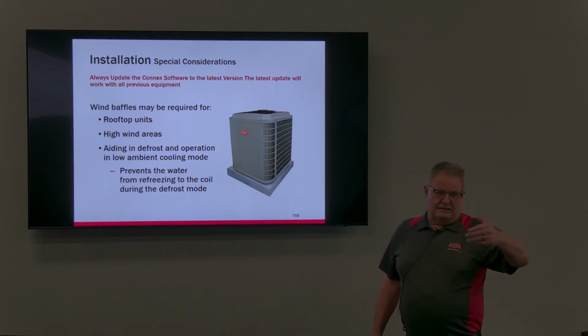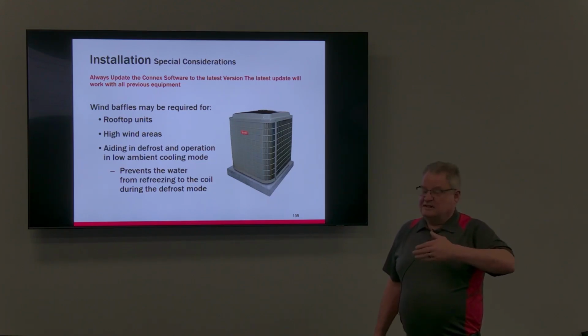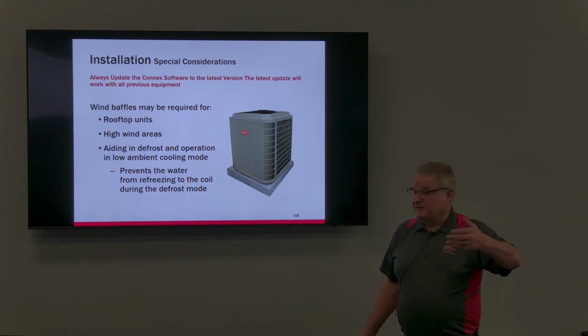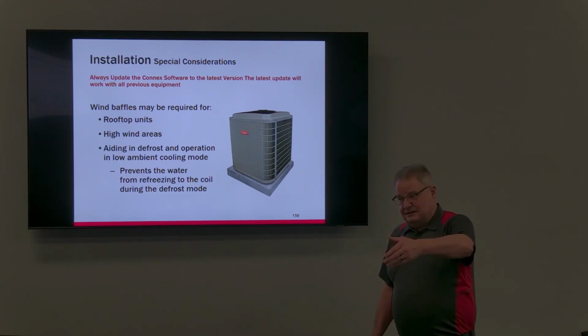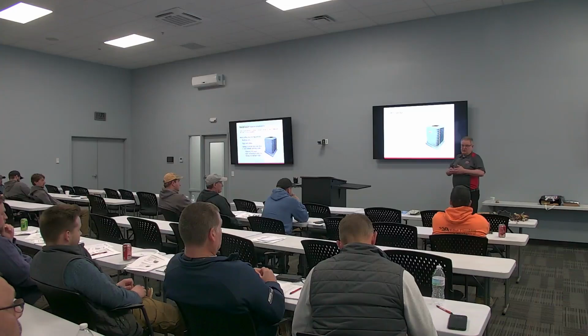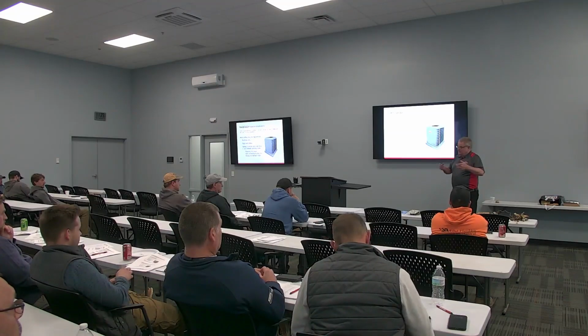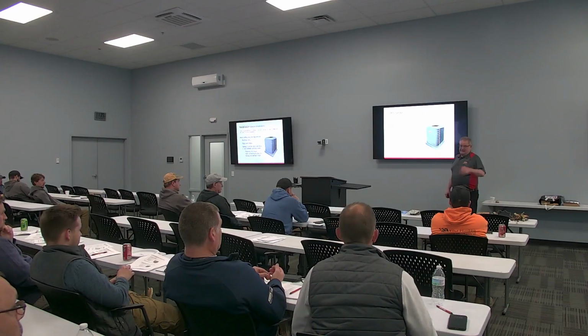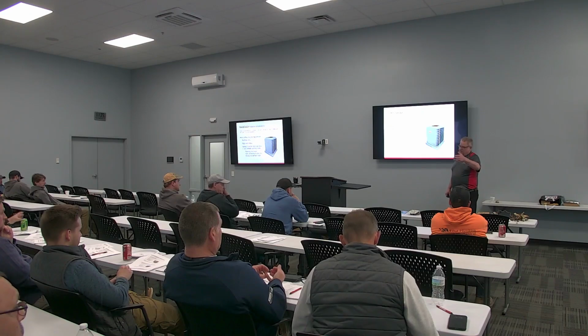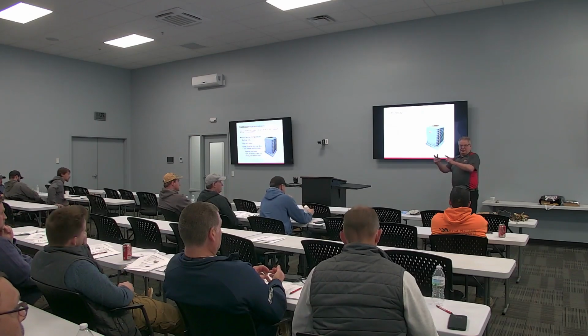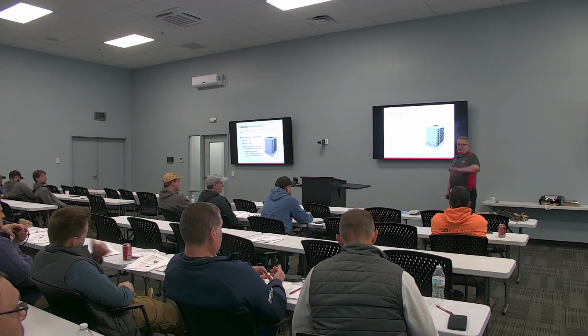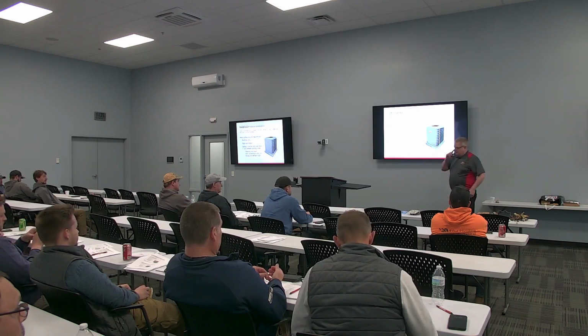Because currently, sometimes on the 987s, the full variable speed furnaces, you go to set the thing up and it'll say, can't see the furnace. I can't find the furnace. And it's just simply an update. So we just got to get the thing powered up, connected to the internet, and then it'll come up and say, do you want to run in demo mode? Yes. And then just let it sit there. And it takes about an hour, or a half hour, 45 minutes or so, and it'll pop up on the screen and say, update available, would you like to download? Hit yes, you're done. So you can go about doing your other stuff while that's happening.